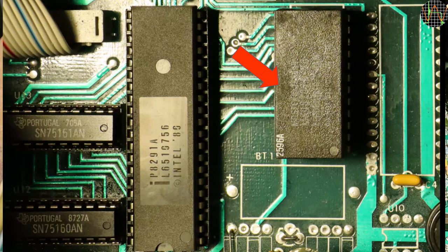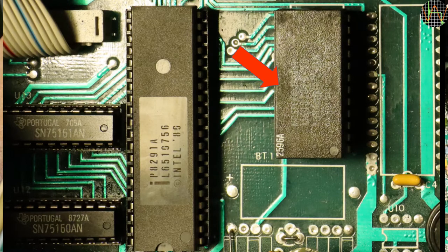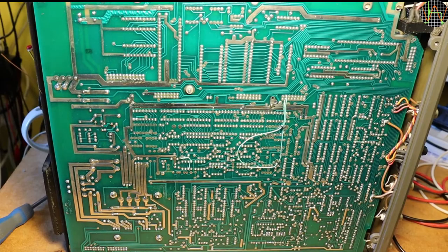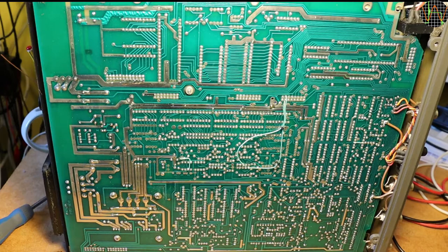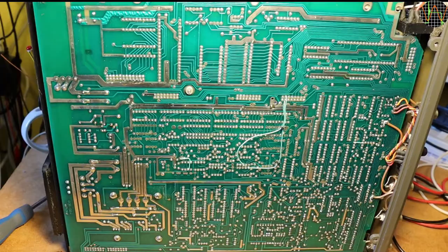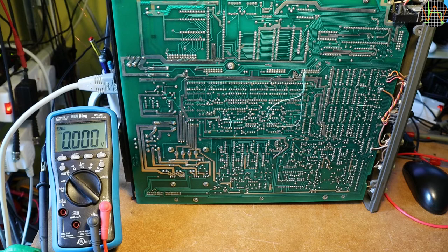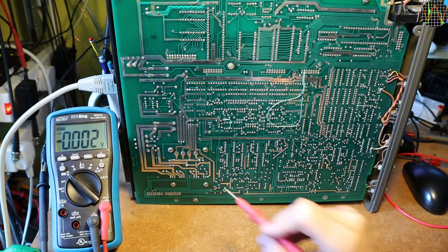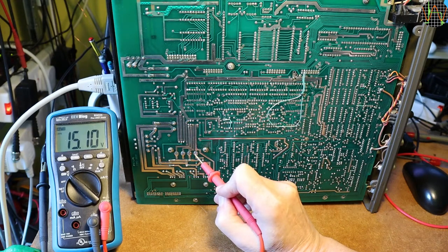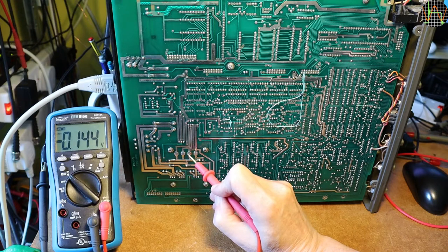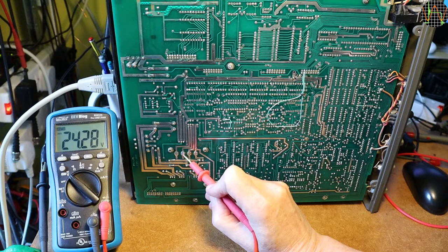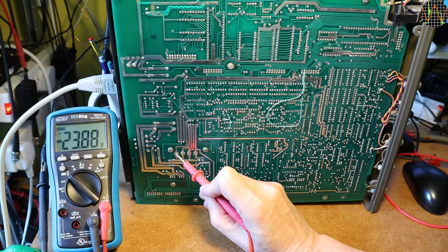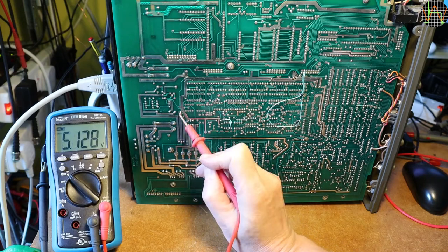Judging from the date codes on the chips, this unit was built sometime in or after 1987, so it is around 34 years old now. The underside of the main board is rather busy but it is easy to see that the top part is mostly the CPU section and the thick traces on the lower left are where the power supply is. The first rule when searching for any error is to check the supply voltages. There are no test points on the component side of the PCB so it has to be done from the soldering side. I fixed the black test lead to the metal sleeve of one of the A201's BNC terminals as a ground. Plus 15V looks okay, but the minus 15V is just minus 0.1V. Plus 24V is okay, minus 24V is good enough, plus 5V looks okay as well. The minus 15V rail is dead.